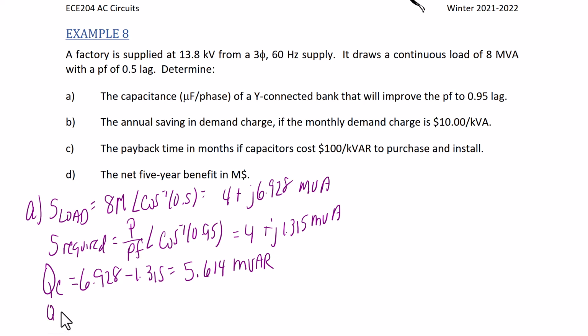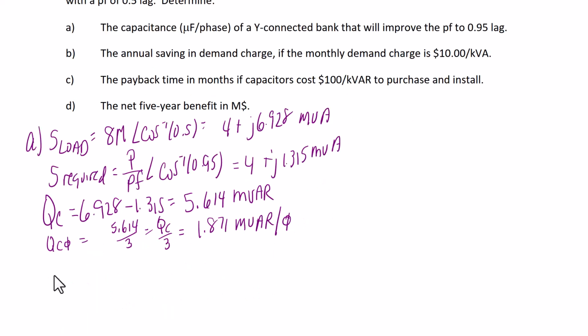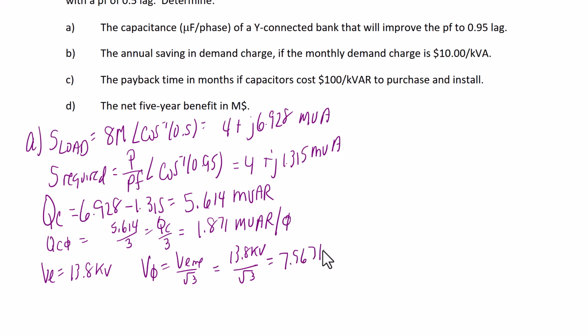So that means that the reactive power we need per phase would be 5.614 divided by 3, which is QC divided by 3, or 1.871 MVAR per phase. So note that we assume that V line is 13.8 kilovolts. So the phase voltage would be V line over root 3. So it's 13.8 kV over root 3, which equals 7.967 kilovolts.